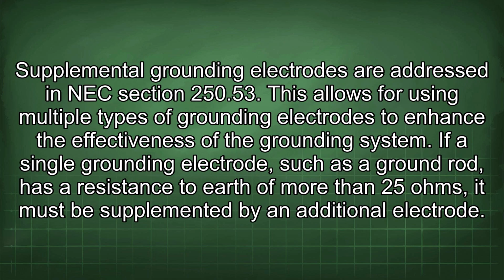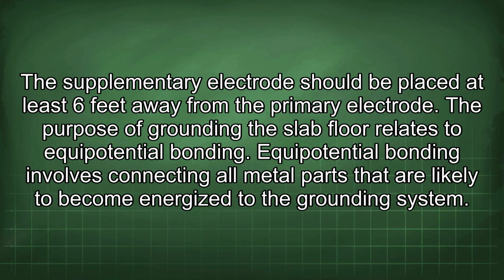Supplemental grounding electrodes are addressed in NEC section 250.53. This allows for using multiple types of grounding electrodes to enhance the effectiveness of the grounding system. If a single grounding electrode, such as a ground rod, has a resistance to earth of more than 25 ohms, it must be supplemented by an additional electrode. The supplementary electrode should be placed at least 6 feet away from the primary electrode.